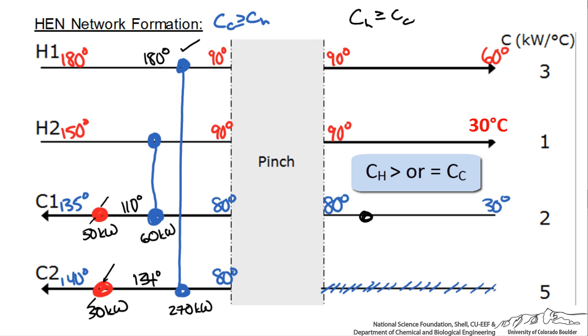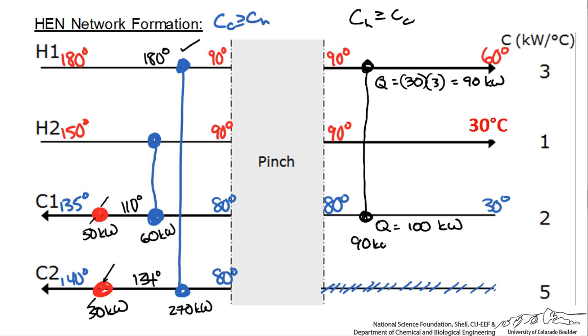Following the rule that it has to be higher, we'll match it with H1 and calculate the Q associated with this. If it were to go from 90 to 60, that would be a temperature change of 30 times 3, which gives us 90 kilowatts. On the bottom, to go from 30 to 80 gives us 100 kilowatts. Our limit is 90 kilowatts, so we'll put that under the exchange.